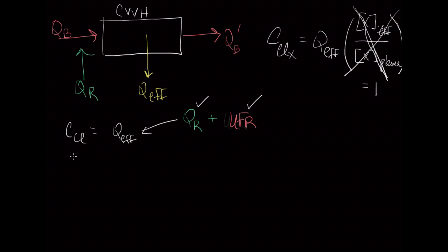Now that would be the end of the clearance equation, except for the fact that you've put your replacement fluid pre-filter. In the previous tutorial, the prerequisite tutorial, you have an understanding of why a pre-filter replacement fluid strategy is different than a post-filter replacement fluid strategy. The equation you have here is one that will calculate your convective clearance if you had your replacement fluid post-filter over here.